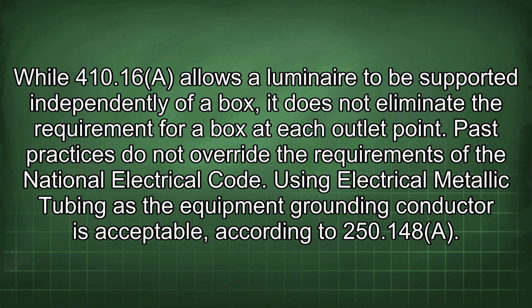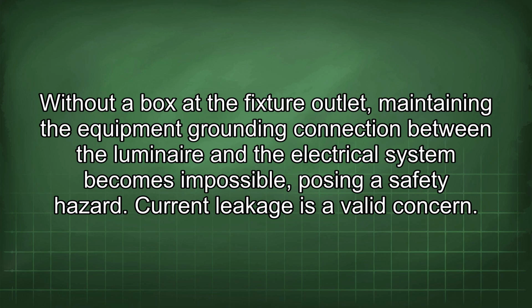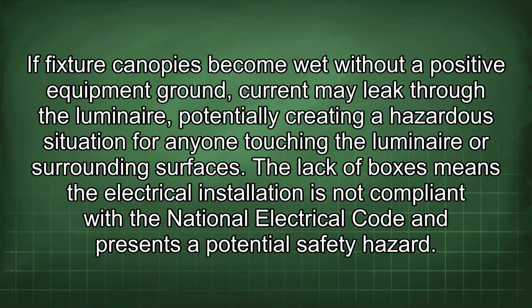Using electrical metallic tubing as the equipment grounding conductor is acceptable according to 250.148a. Without a box at the fixture outlet, maintaining the equipment grounding connection between the luminaire and the electrical system becomes impossible, posing a safety hazard. Current leakage is a valid concern. If fixture canopies become wet without a positive equipment ground, current may leak through the luminaire, potentially creating a hazardous situation for anyone touching the luminaire or surrounding surfaces.